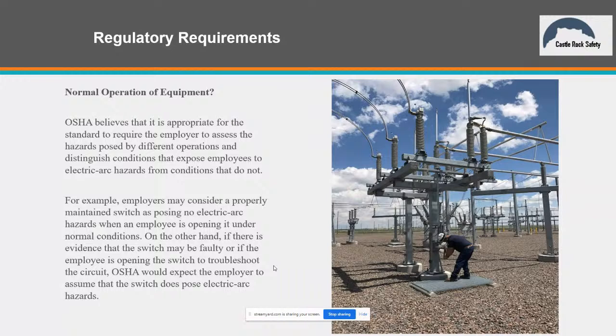If you start at the baseline and you're following 1910.269, and that switch has been installed properly, and there's no reason to believe there's a failure, there would be no arc flash clothing required for that guy, unless the incident energy is above 2 calories. Now, NFPA 70E uses 1.2 calories. 1910.269 has a 2-calorie boundary. So there's a little bit of difference there, and I can explain why that is.